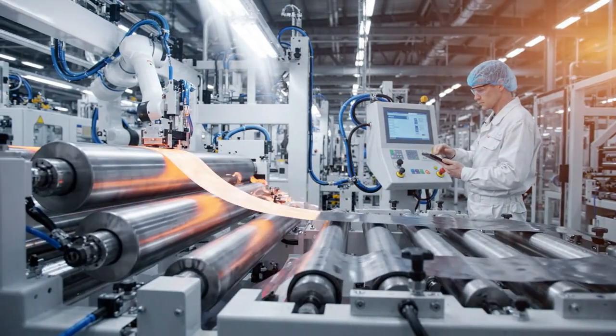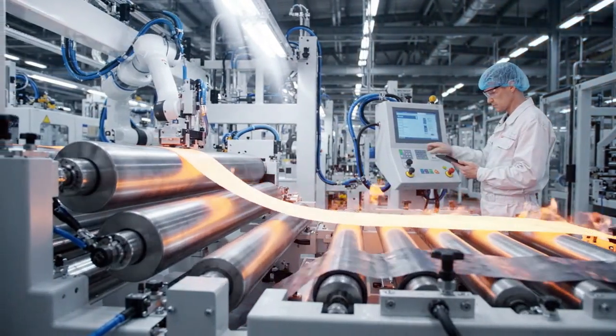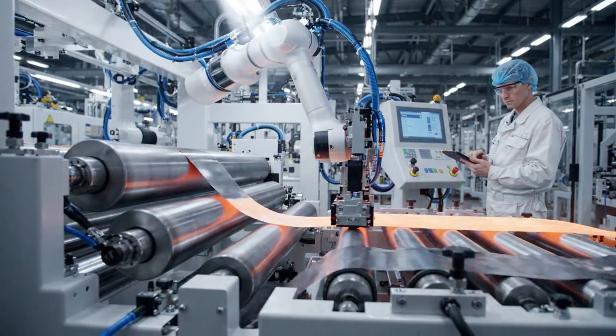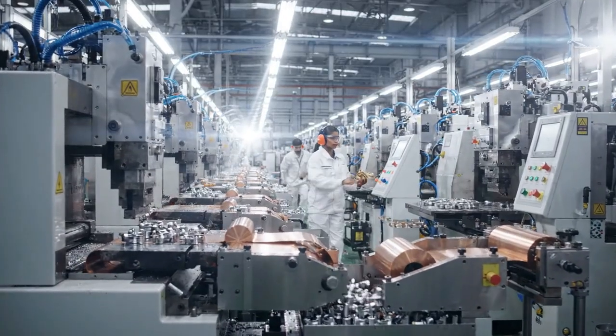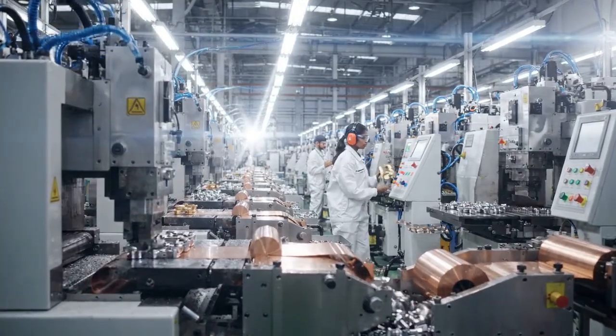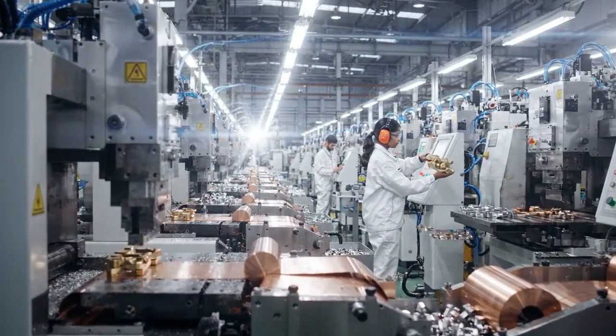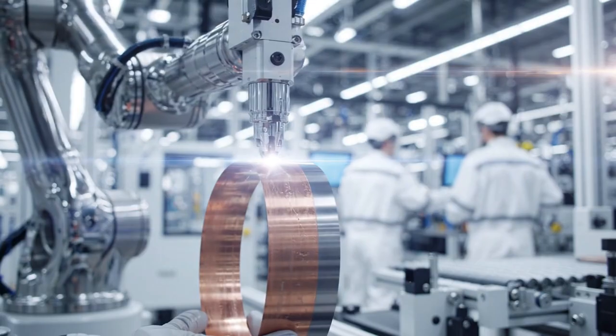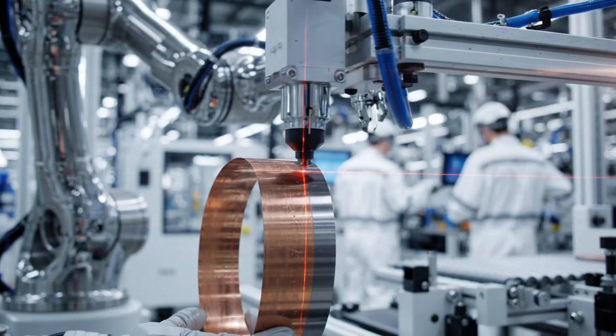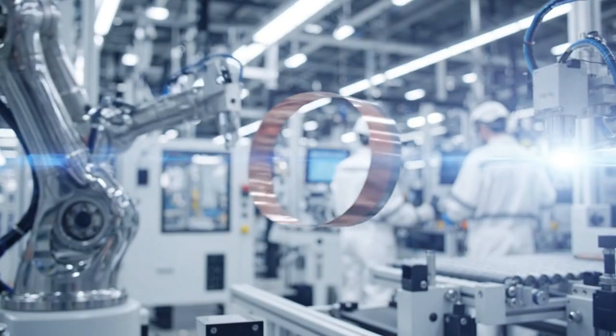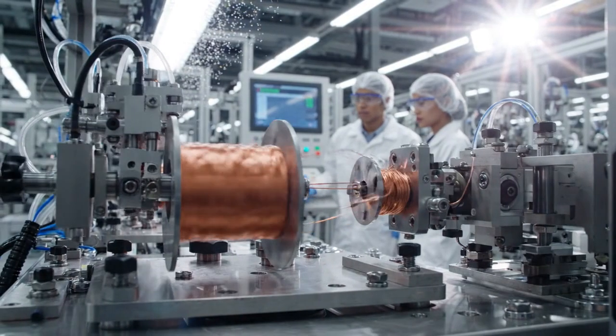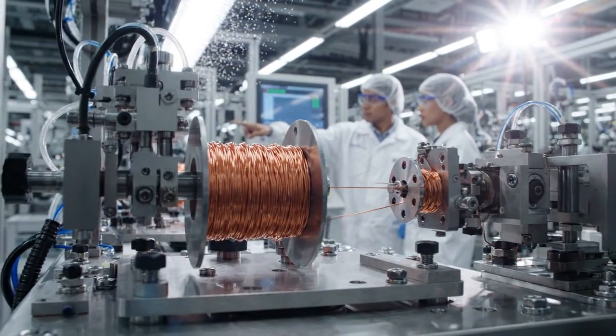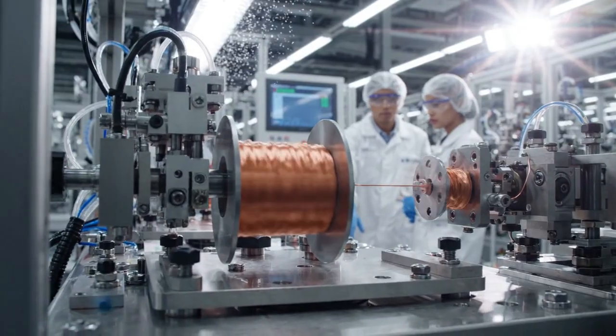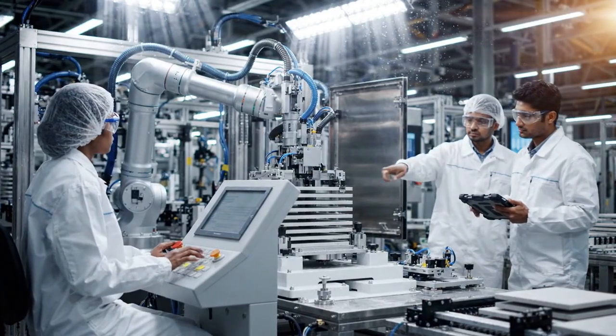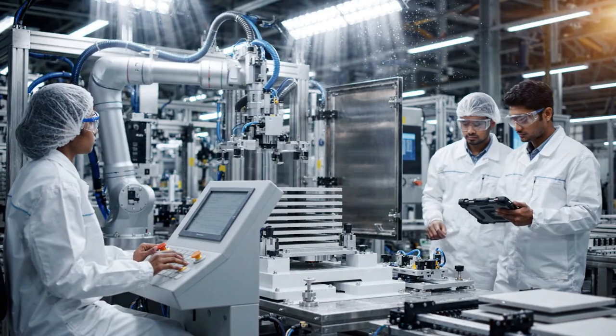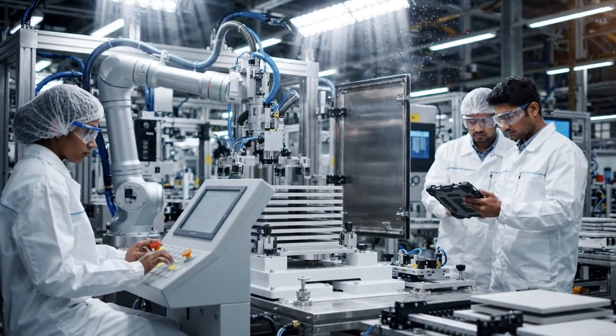Roll bonding fuses the high-expansion and low-expansion metals into a single composite strip. The bonding must be perfect. Bimetallic calibration determines the exact current at which the breaker will trip. Each element is individually formed to match its rated current specification. Arc chutes contain multiple parallel plates that split the fault arc into many shorter arcs, cooling and extinguishing the discharge that would otherwise sustain itself.